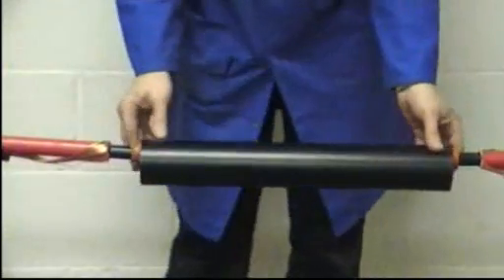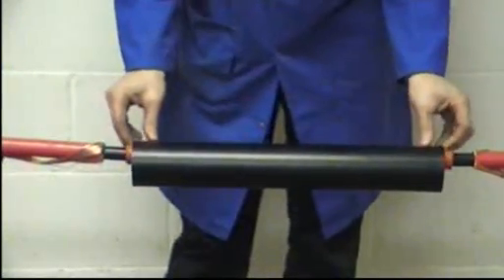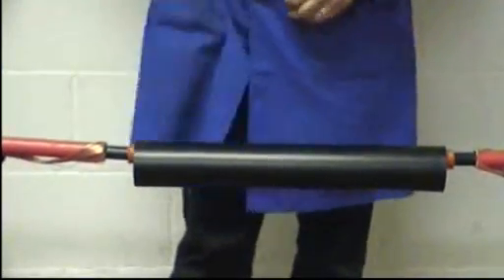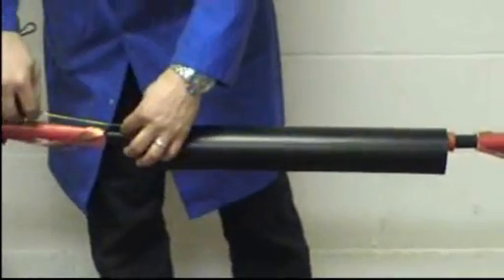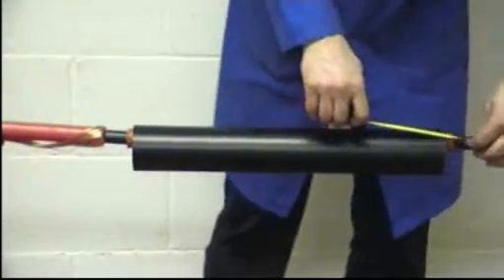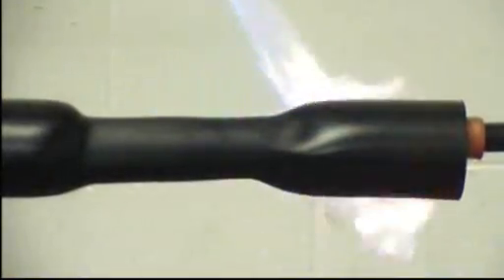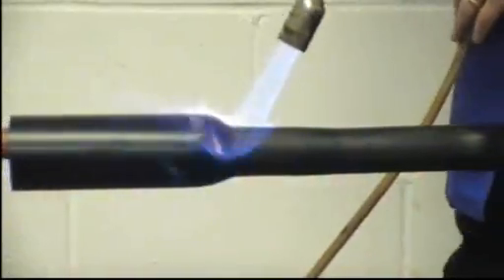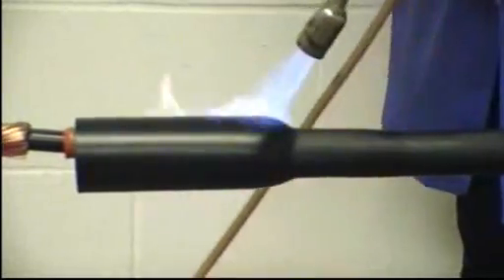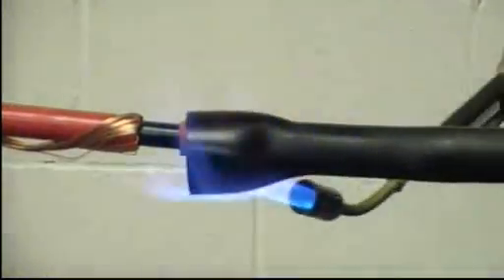We now position the combined insulation conductive tube. Center this up on the previously applied tubes, and once again, starting at the center, shrink in an even manner to one end at a time. Now, at 12 kV voltage, this would be the only tube fitted.